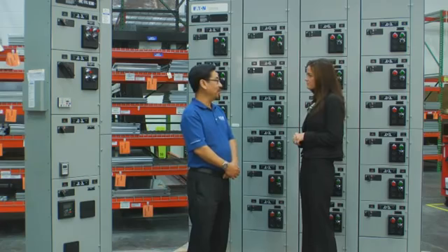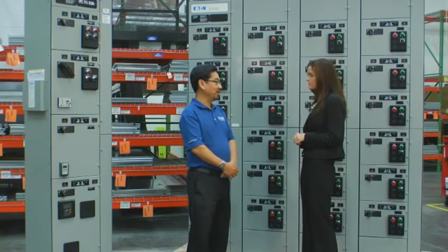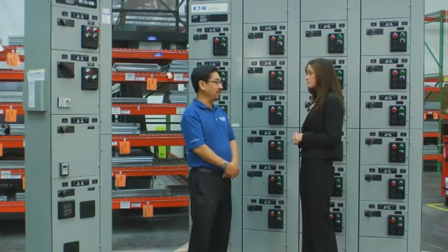And we can take safety even a step further than that. We can offer FlashGard MCC with Eaton's patented arc reduction maintenance system, or ARMS as we call it. ARMS can greatly reduce the amount of energy that's generated during an arc fault event. And less energy means less damage and danger if an event like this ever happens to you.